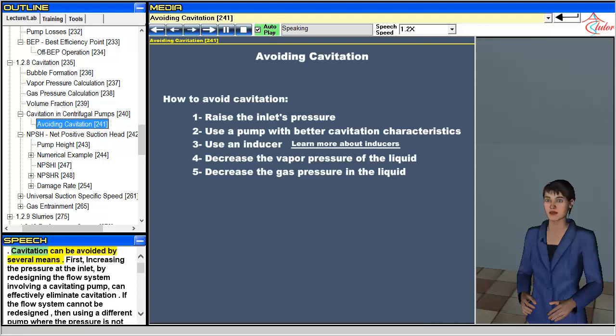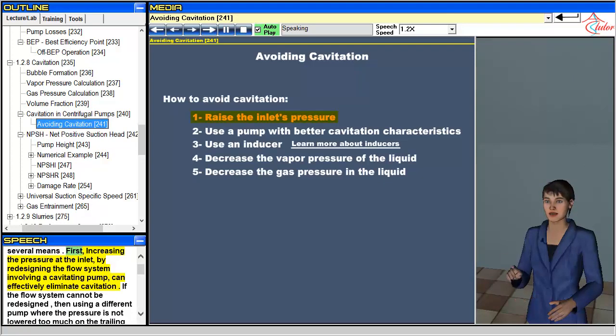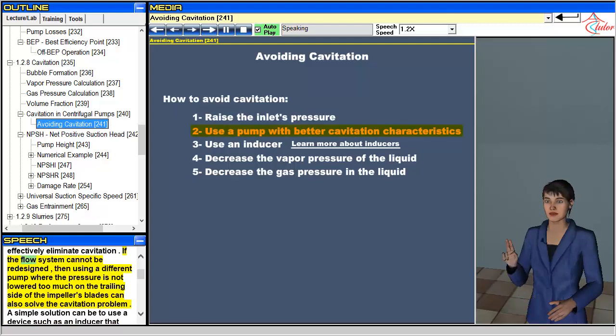Cavitation can be avoided by several means. First, increasing the pressure at the inlet by redesigning the flow system involving a cavitating pump can effectively eliminate cavitation. If the flow system cannot be redesigned, then using a different pump where the pressure is not lowered too much on the trailing side of the impeller's blades can also solve the cavitation problem.